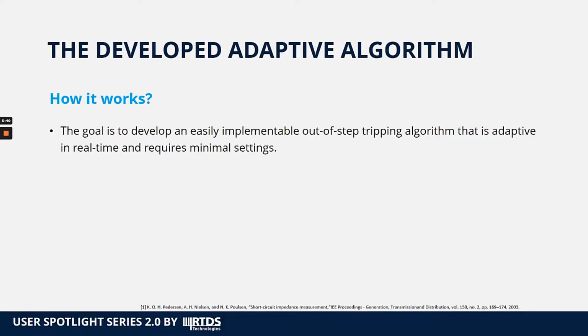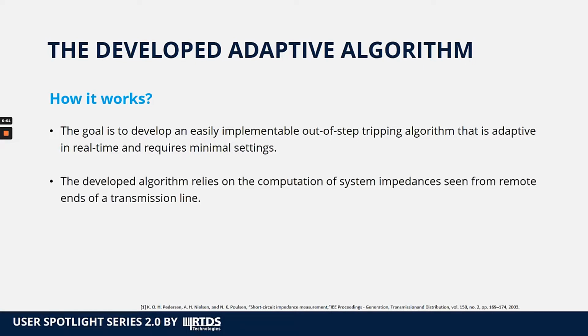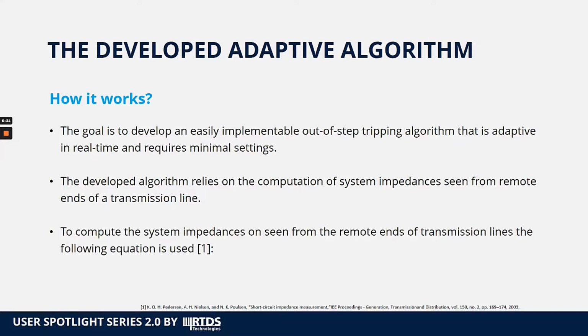So, as I mentioned, the goal was to develop an easily implementable out-of-step tripping algorithm which requires minimal settings and can adapt to different grid conditions in real time. And what we came up with is to try to rely on computation of system impedances as seen from both ends of a transmission line, so that we can make the protection algorithm adaptable to different types of grid conditions. To do this, we compute the impedances on the remote ends of the transmission line using the following equation, where an equivalent impedance is calculated from two sampled values in voltage and current phasors using wide area measurements.